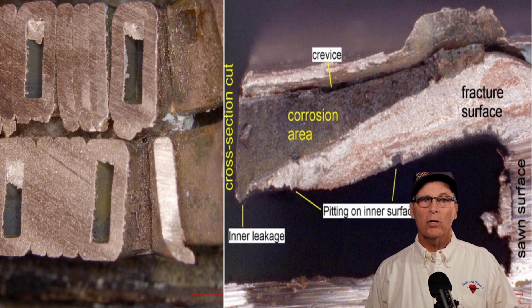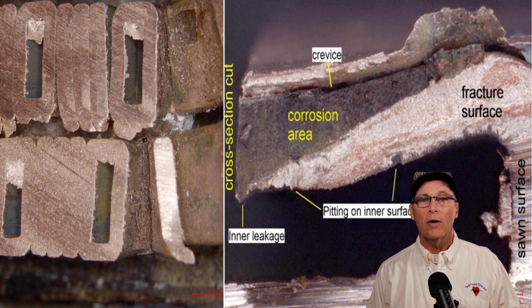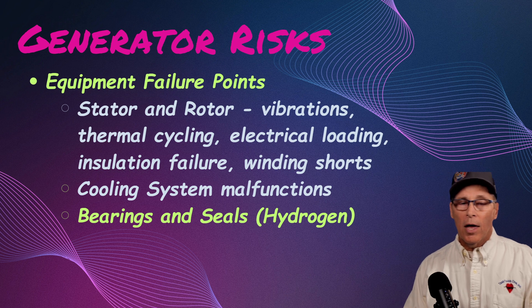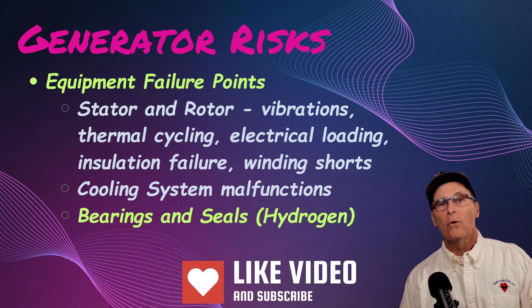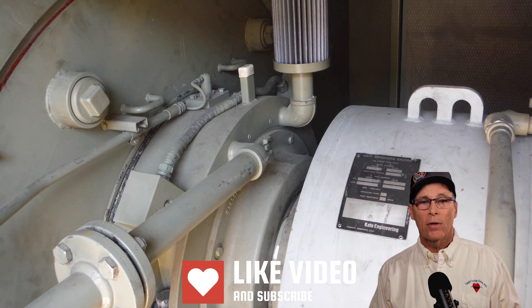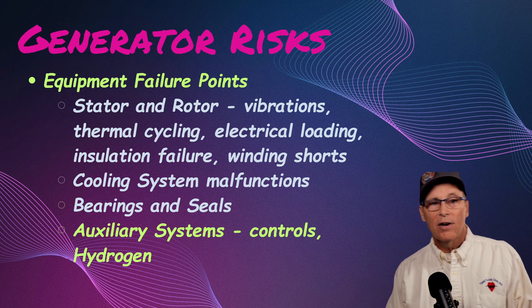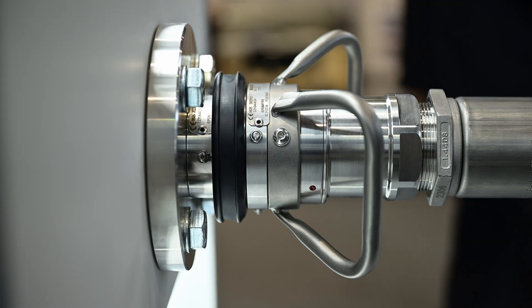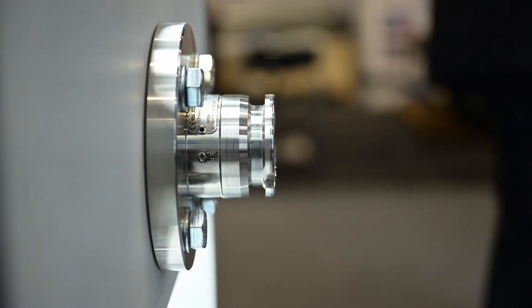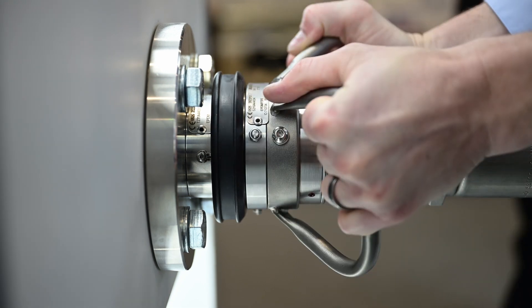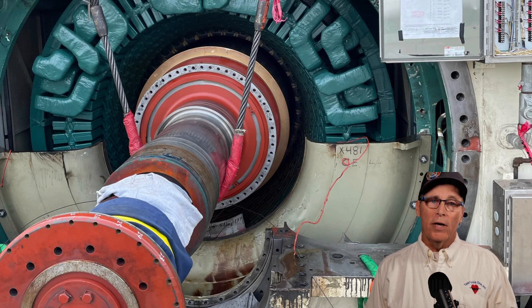Here's a close-up of the inside of stator bars from an investigation where we had hydrogen leaking due to crevice corrosion cracking. Remember — we have hydrogen in these machines, so we have to keep that seal oil flowing or we risk a fire. This is a close-up of the bearings on one of these machines. For auxiliary controls, you have a complete hydrogen system — you have to manage how you're adding hydrogen, monitoring it for leakage, and how often you're changing your bottles.